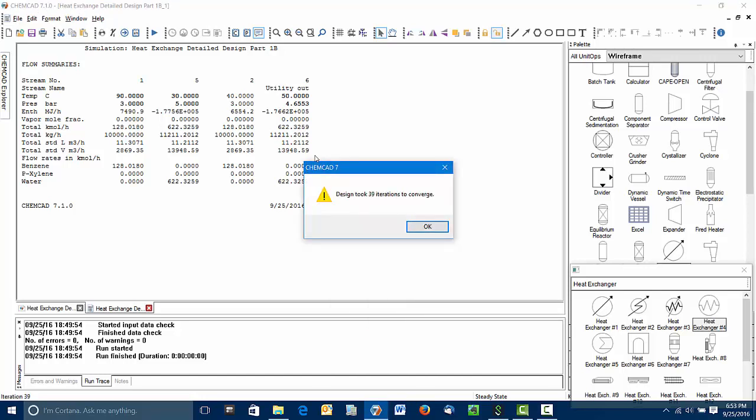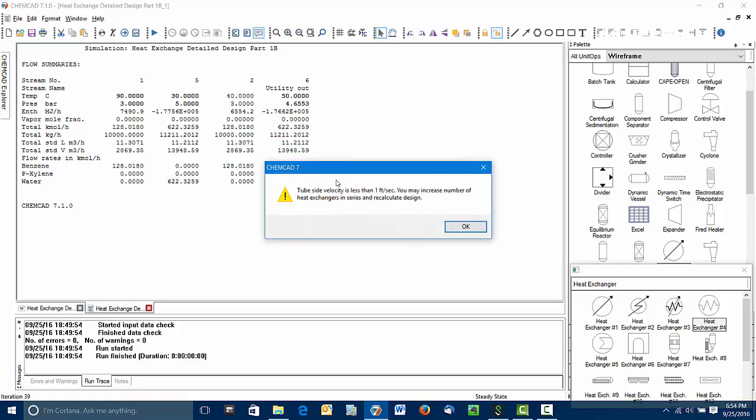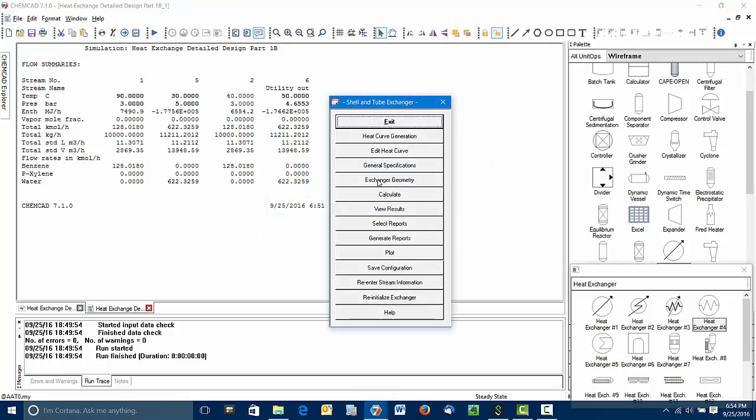And you can see it went through 39 iterations. What is happening here is ChemCAD is doing the pressure drop calculations, estimating the heat transfer coefficients, looking at the mechanical design of the exchanger until we meet the pressure drop specification and the thermal specification. ChemCAD is also changing the cooling water rate as we go as well. Now we have a warning here. The tube side velocity is too low. Another warning, the shell side velocity is too low. So this design is not good as it stands.